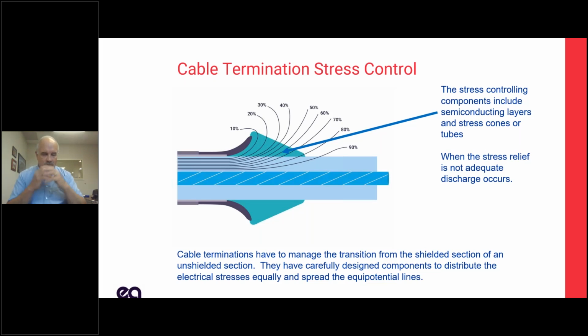When we talk about stress control, we talk about cables: we've got this wonderful engineered cable assembly that's shielded. It's got semicon layers, so I can go a kilometer, 2 kilometers, whatever, and I know the field inside that cable is perfectly even. And I know that that field is less than the withstand capability of the insulation. So I am good from end to end. The problem is, a cable's not much good unless I can get the electricity through it. So I've got to terminate that cable in something where the conductor comes out of the insulation. And if I were to just cut that insulation back like I was dealing with a 600 volt cable, I would have this massive problem right where the insulation was cut.